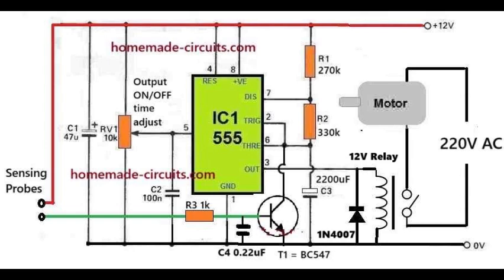The timer keeps the pump motor on for 15 seconds. If water is not detected, the pump is switched off for the next 15 minutes. After 15 minutes, it repeats the water detection process and this goes on until water is finally detected in the pipe.